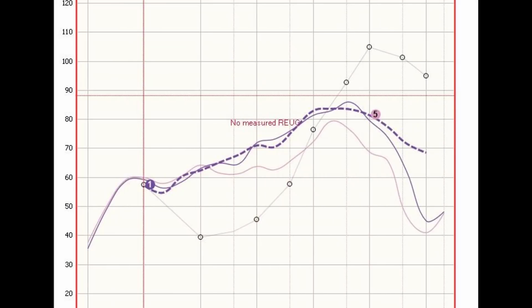I'm going to show you some screenshots of first fit measures that I've done on hearing aids that are programmed by the manufacturer's software, and then I'm going to show you what I actually adjust them to, to make sure that they're meeting a prescription. In this screenshot, the pink line illustrates the manufacturer's first fit estimate of amplification, and the purple line shows the programming after adjustments made using real ear measurement. After verifying the amplification using real ear measurement, we now know that this patient is getting the correct amount of amplification to accommodate their hearing loss.